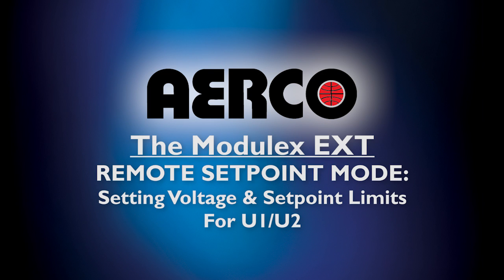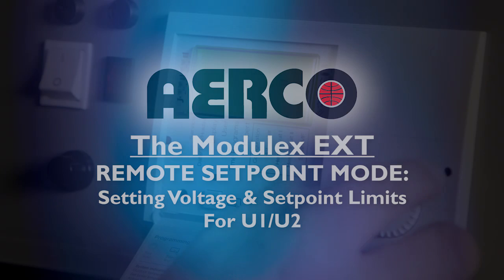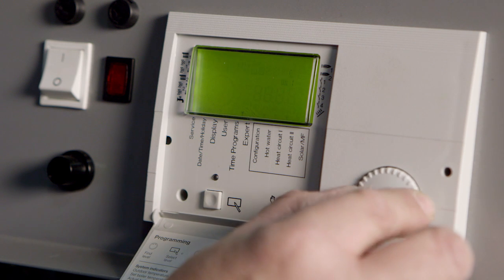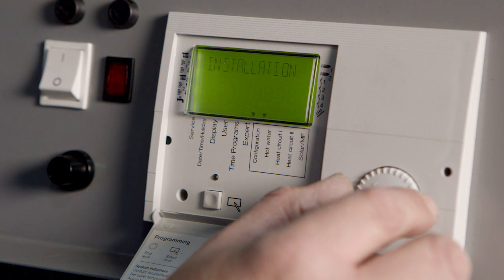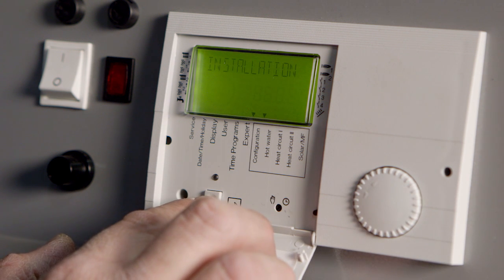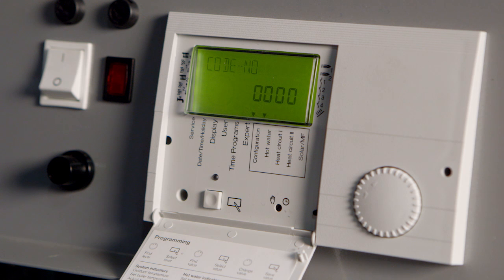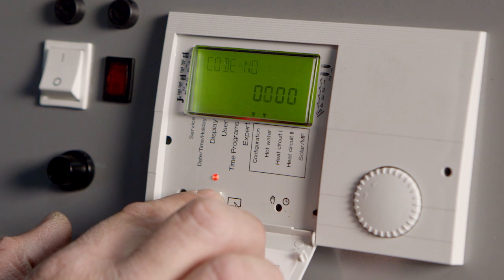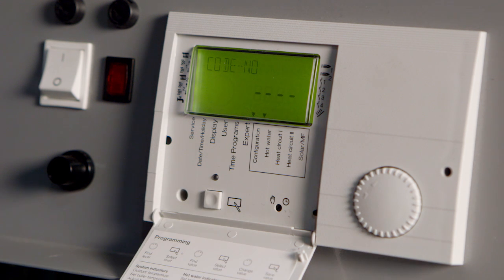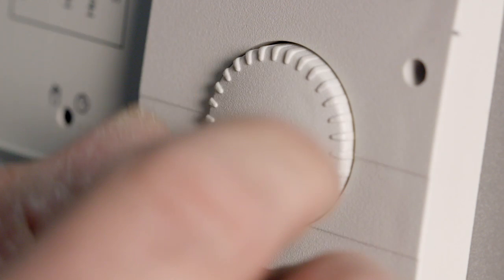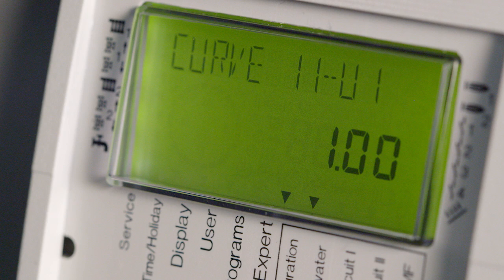To set the voltage limits corresponding to the minimum and maximum allowable set points, refer to the following step-by-step demonstration. Begin by scrolling through the menu to the Installation submenu as shown. Hit this button. The display will show you code number, which means it's requesting that you enter a valid code to continue. Enter the code, 4 zeros, by pressing the program key 5 times like this. Next, turn the rotary knob clockwise to access curve 11-U1 as shown.